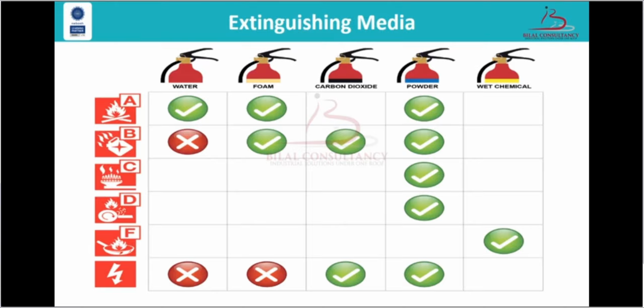Wet chemical fire extinguishers are specifically designed to deal with high temperature fires greater than 360 degrees Celsius. It reacts with burning oil to form thick soap, cooling and emulsifying the oil, putting out the flame and sealing the surface. Moving forward toward the siting, maintenance and training related to fire extinguishers.